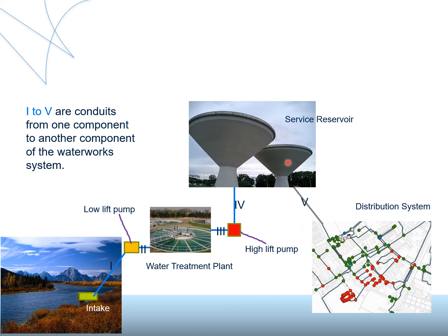But because of the service reservoir, you don't need to have these other components with the same design capacity. You can design anything before the service reservoir for the maximum daily demand plus reserve. You don't need to design for peak hourly demand because the service reservoir will balance the demand.